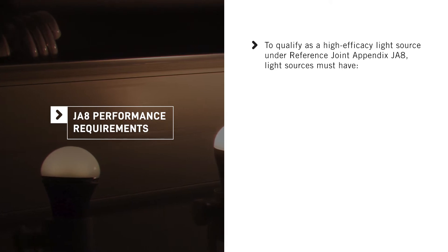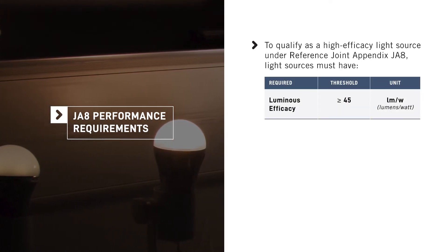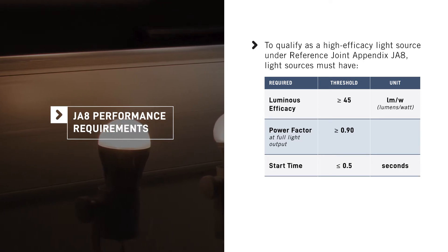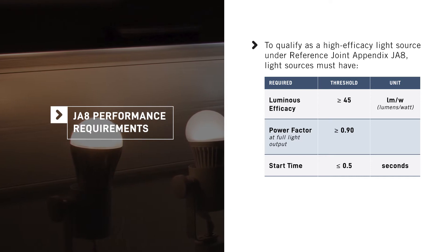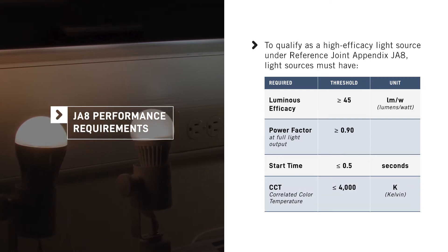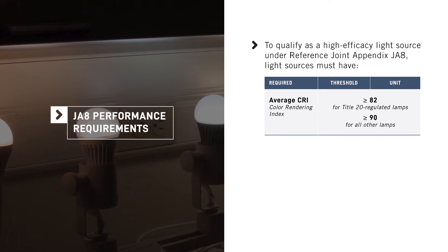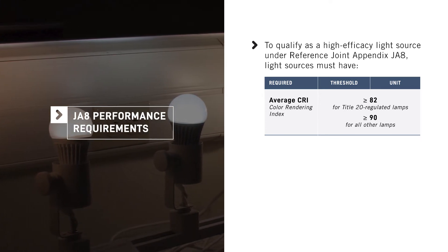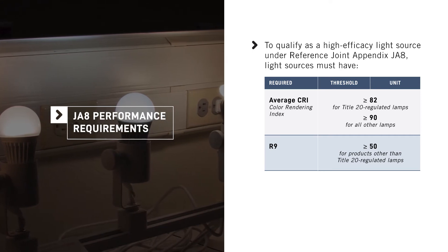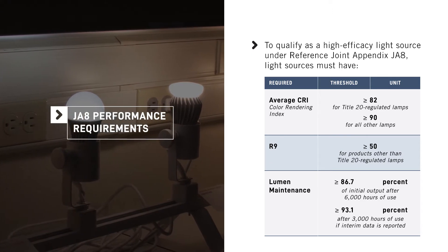To qualify as a high efficacy light source under Joint Appendix JA8, light sources must have a luminous efficacy greater than or equal to 45 lumens per watt. The power factor must be greater than or equal to 0.90 at full light output. Light source start time should be less than or equal to one half second to prevent delays between applying power and the start of illumination. The CCT should be less than or equal to 4000 Kelvin. The CRI must be greater than or equal to 82 for Title 20 regulated lamps, and greater than or equal to 90 for all other lamps. The R9 must be greater than or equal to 50 for all products other than Title 20 regulated lamps. Lumen maintenance must be equal to or greater than 86.7% of the initial output after 6,000 hours of use.